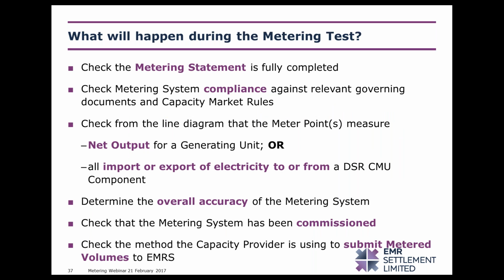So what happens during the test? As I mentioned earlier, it's checked for completeness, and following that, we check to make sure the metering system is compliant against the relevant governing documents which I mentioned before, such as the codes of practice or the relevant balancing services agreements. We use the line diagram to check that the net output for a generating unit is measured correctly, or for a DSR CMU that the import or export of electricity to or from has been measured correctly. We also determine the overall accuracy using the information supplied in the metering statement, as Ian has just gone over, and that the metering system has been commissioned correctly. And we also check the method for submitting metered volumes. You may get more details of submitting metered volumes through Working Practice 195, which is available on the EMRS website.